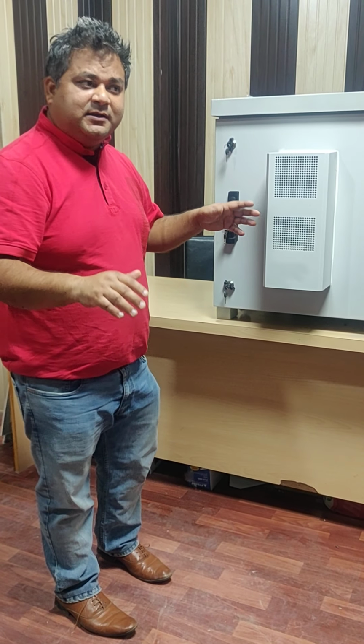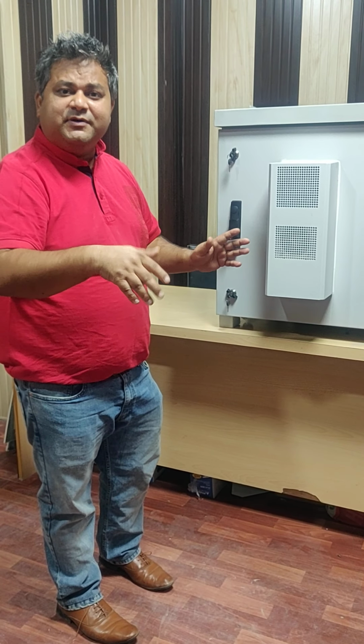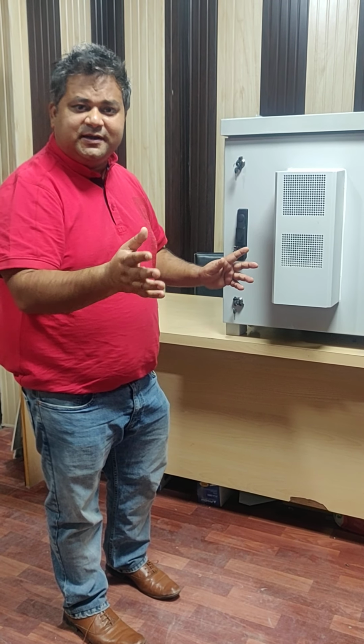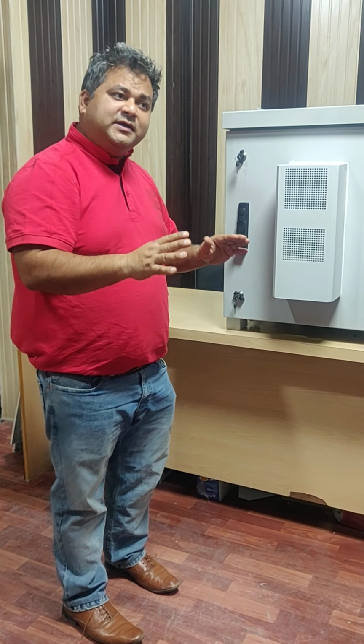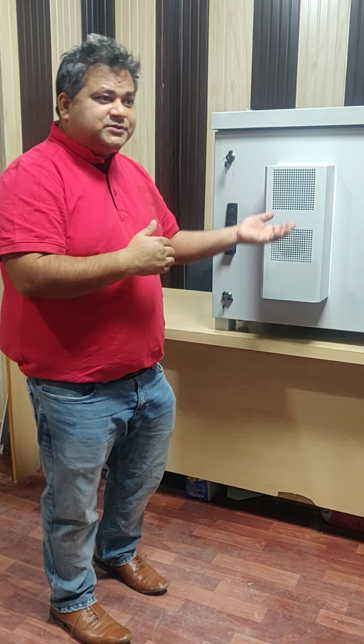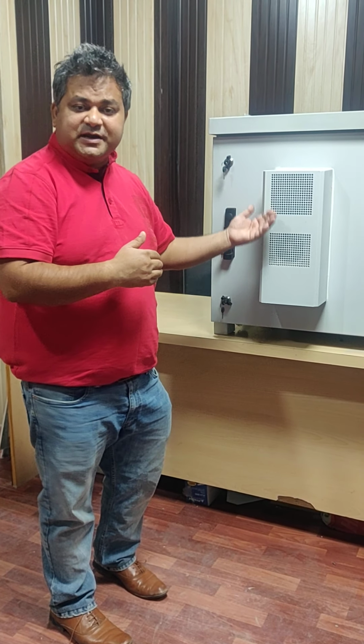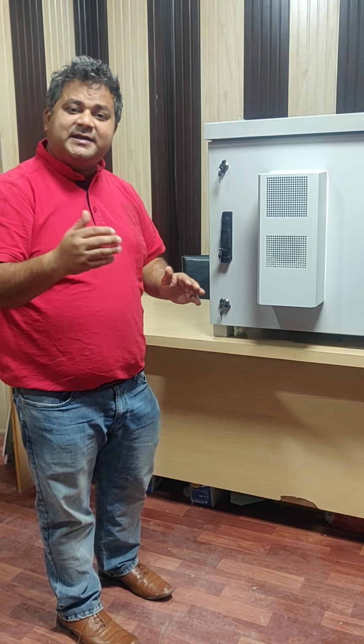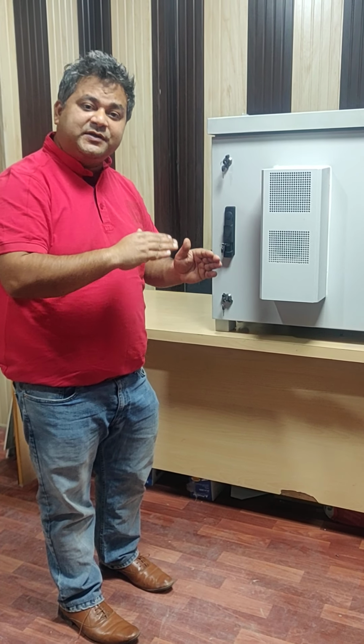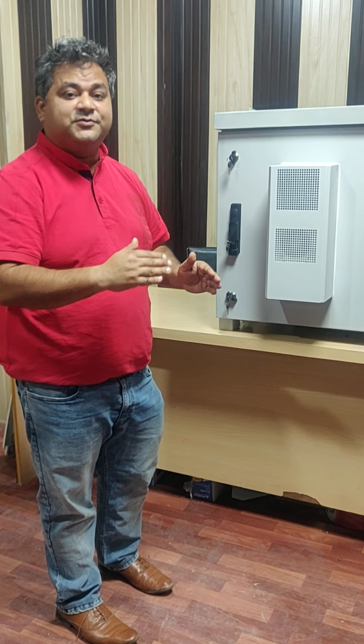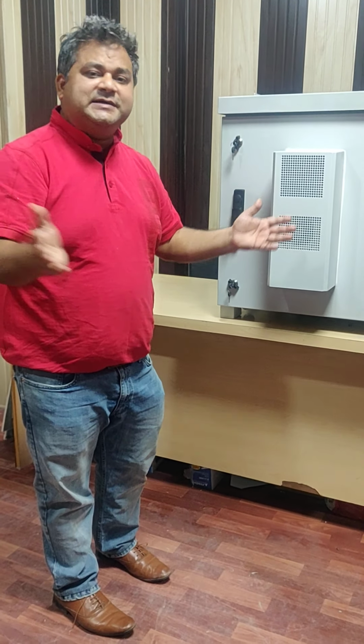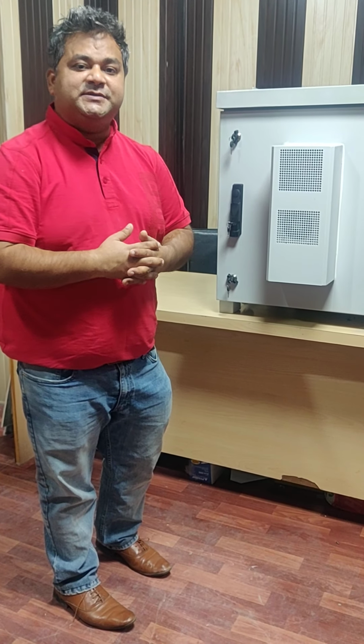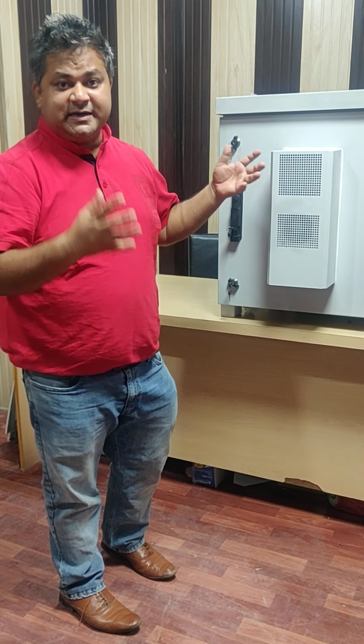So it will maintain around 21, 22, or sometimes 20 degrees. But if we activate all the network switches, one or two switches, plus one UPS, it can reach up to 23, 24, 25, even 26 degrees - which I think is a sufficient and good temperature to maintain active components inside any cabinet.